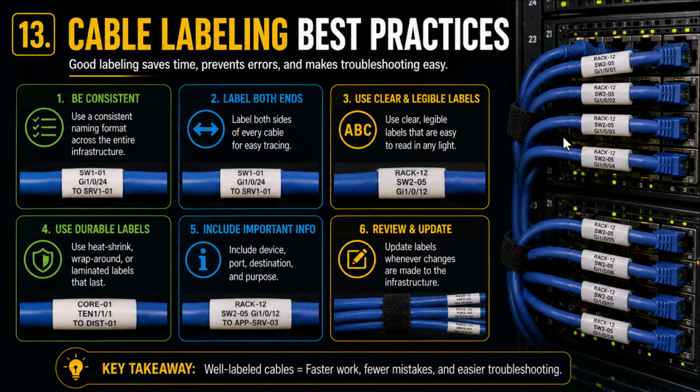Now imagine you have a rack with thousands of servers and hundreds of cables. How do you know which cable goes where? That's where labeling becomes critical. A useful label should help identify both ends of the connection. For example, it might tell you the source device and port, destination device and port, or reference information used in your cabling documentation. This becomes extremely valuable during incidents. Instead of guessing which cable belongs to which interface, you can trace the path systematically.